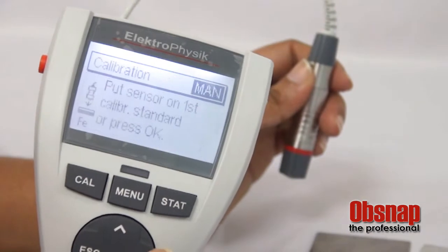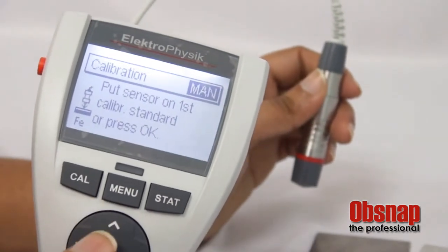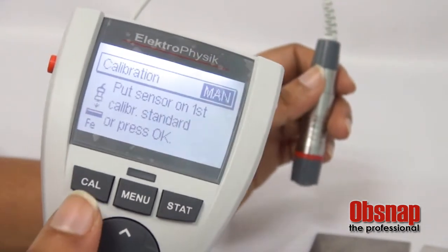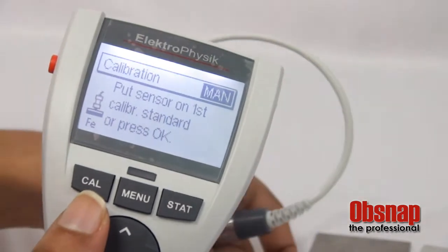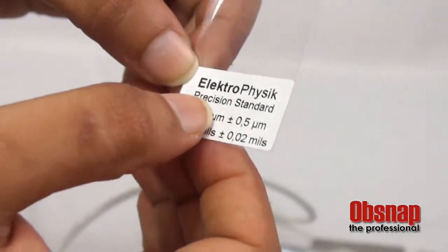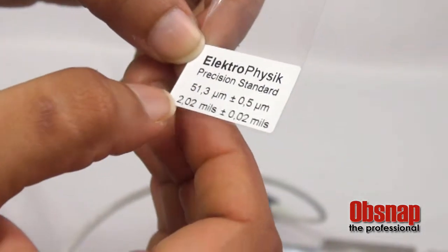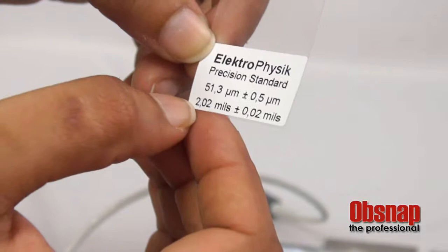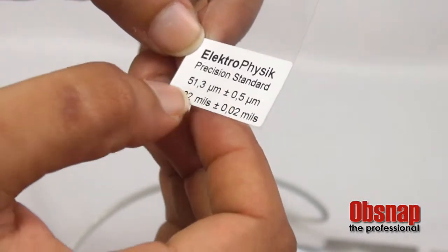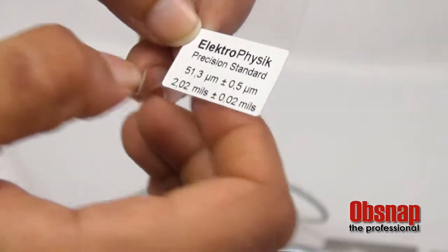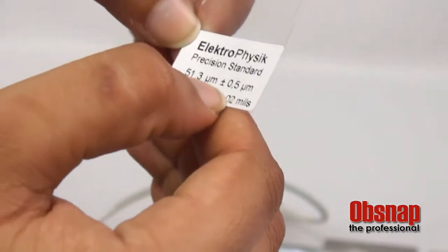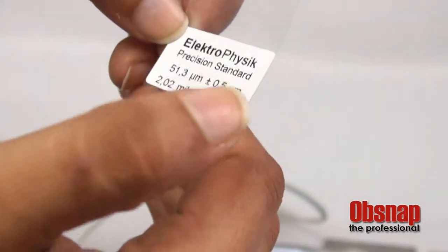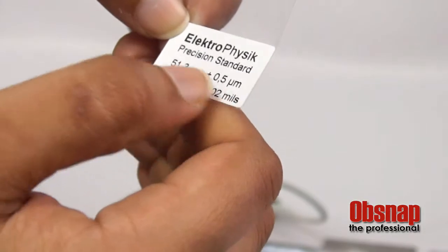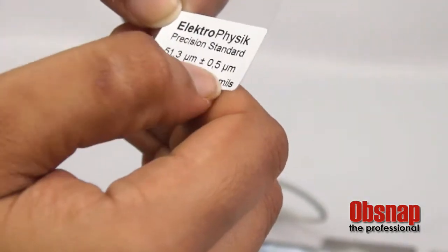Then click OK. Next, it will ask you to put the sensor on the first standard calibration foil. You can choose standard calibration foil. This is the precision standard foil that we use for calibration purpose. A sample of the calibration foil that we can perform calibration: 51.3 micrometer plus minus 0.5 micrometer is the tolerance. This is the acceptable range for the calibration purpose.